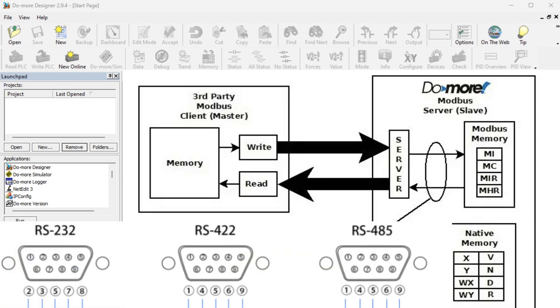The media or wiring used depends on the actual type of Modbus protocol used. Serial communication will usually use RS-232 or RS-485 media — this Modbus protocol is RTU or ASCII. All devices must have the same wiring and Modbus protocol before communication can occur.